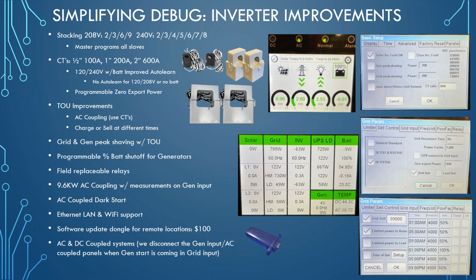We've got programmable percent battery shutoff for generators, so if you don't want to charge your battery all the way back up to full, you can change that set point whenever the generator is called for. And of course, you also have the other way around, where if your battery drains to a particular point, we have 2-wire start, and we can fire up your generator to charge the battery if you hit a particular percentage.